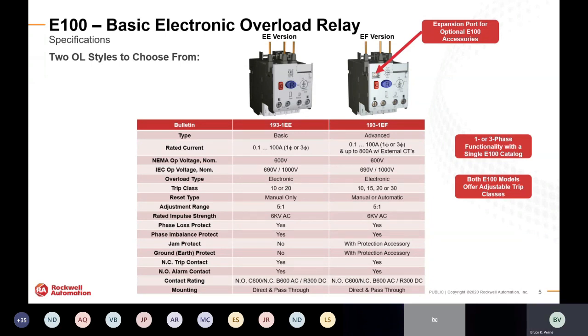If we look over at the advanced version on the right, again, the same current range of 0.1 to 100 amps. And then this is the version that also offers up to 800 amps with external CT configurations. Again, the same single phase or 3-phase configuration. And then in addition to the 10 and 20 trip classes, we add 2 other additional trip classes of 15 and 30. And then the advanced version also offers a manual or automatic reset mode. Then you'll also see in the image in the top right of the screen there's a small expansion port, which we'll talk a little bit more about coming up, but that is an expansion port for optional E100 accessories that you can also connect to further enhance the protection application for your E100 solution.